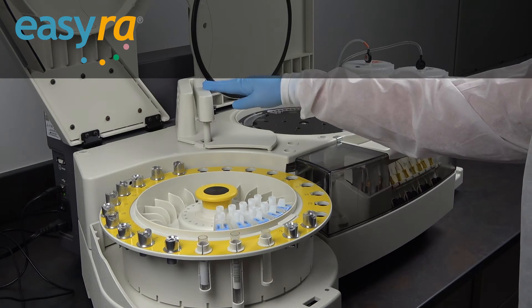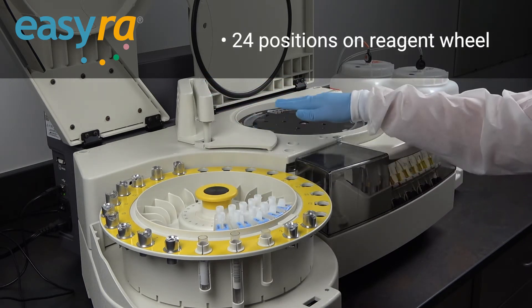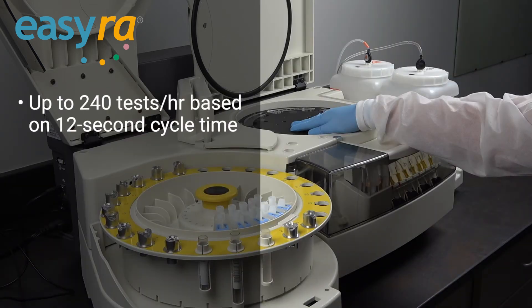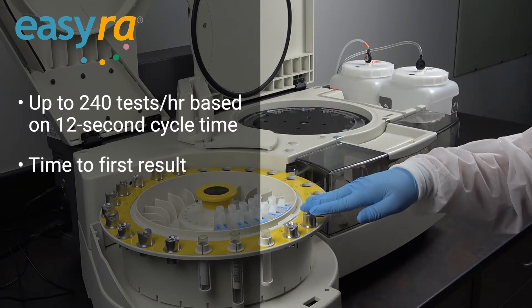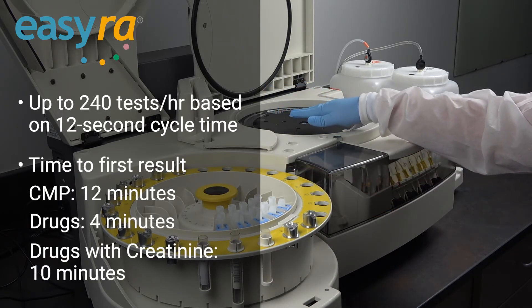The sampling probe picks up the reagent from the 24-position reagent wheel and adds it to the reaction cuvette where it incubates at 37 degrees Celsius. Then the sampling probe adds the sample to the reaction cuvette. They are mixed, and once the test is completed, the EasyRA produces a chartable result.